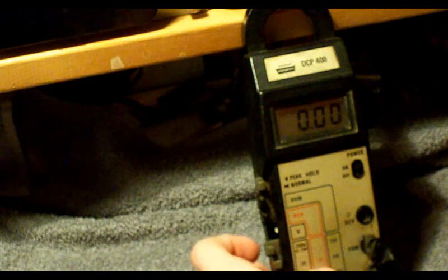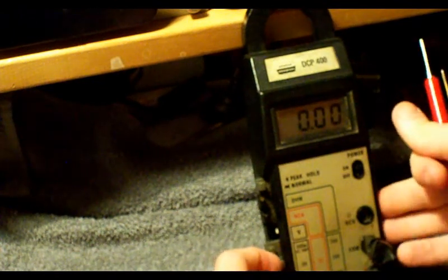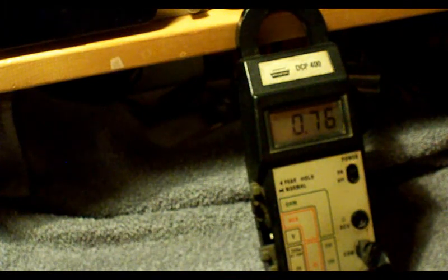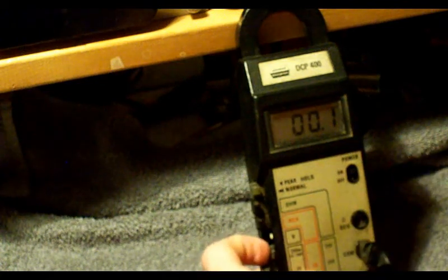And now we're going to go ahead and energize the primary. Okay, the primary winding is now energized. I'm going to go ahead and hook the meter across the secondary. Now volts, let's see, 20 volts. So we're going to go ahead and read across the secondary winding. Okay, what's going on here? I'm getting, okay, the variac's hooked up. There we go. Sorry, the meter was just set on the wrong range.